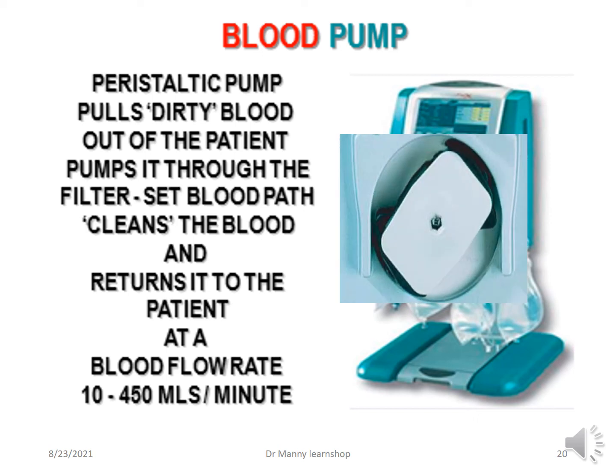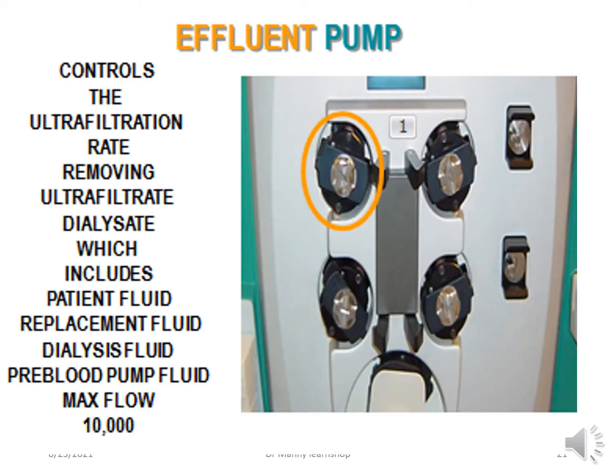That's the blood pump. Then you've got the effluent pump. The effluent pump is in the upper left-hand corner as we face the machine, and it controls the ultrafiltration rate, removing ultrafiltrate, dialysate, which includes the patient fluid, replacement fluid, dialysis fluid, pre-blood pump fluid, and the maximum flow rate that can be removed is 10 litres per hour.